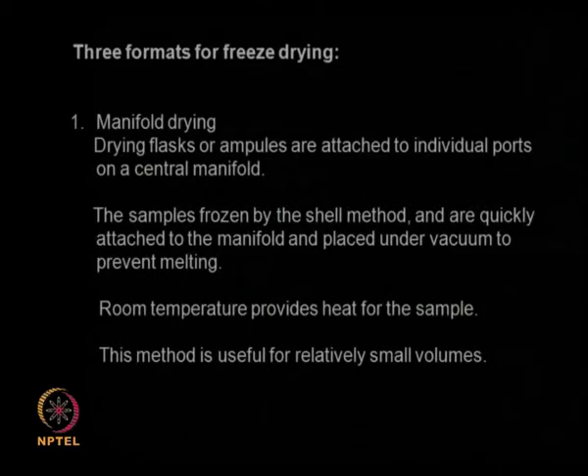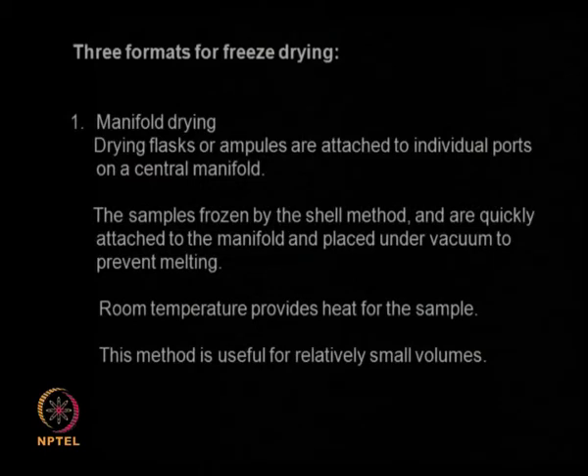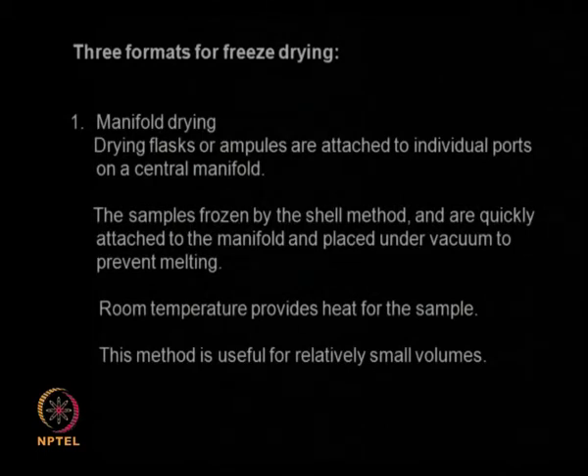There are different types of freeze drying. One is called manifold drying — you have a central manifold to which you attach many ampules or drying flasks. The samples are first frozen separately by the shell method, then attached to the manifold. Vacuum is applied to prevent melting, and then the temperature is brought up to room temperature, which provides sufficient heat to remove the moisture as vapor — ice goes directly into vapor. This method is very good for small volumes.